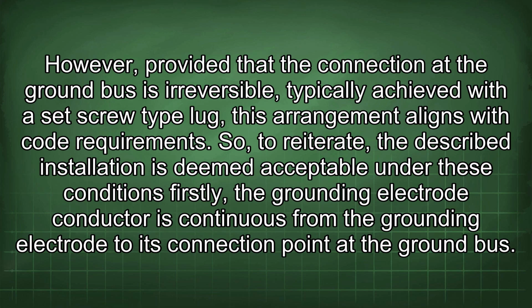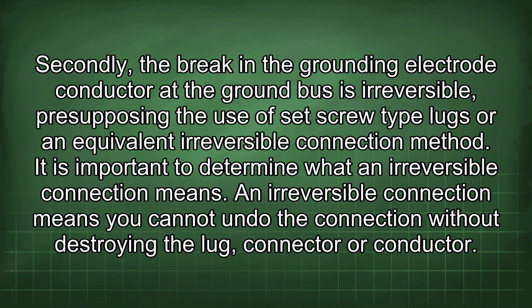Firstly, the grounding electrode conductor is continuous from the grounding electrode to its connection point at the ground bus. Secondly, the break in the grounding electrode conductor at the ground bus is irreversible, presupposing the use of set screw type lugs or an equivalent irreversible connection method.